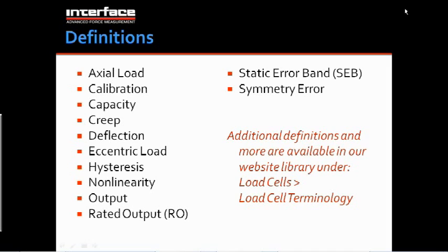Calibration, again, we'll talk about some of the parameters that need to be met. Calibration is performed after the complete assembly of the load cell has been carried out. From there, let's talk about capacity, which is how much force, how much weight, how much load can be applied to the load cell.